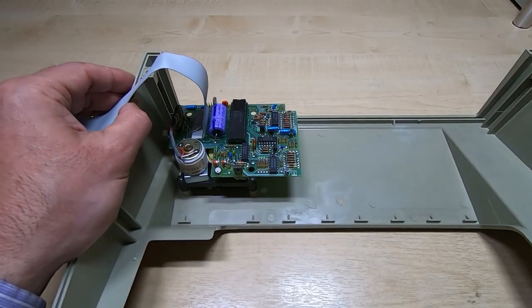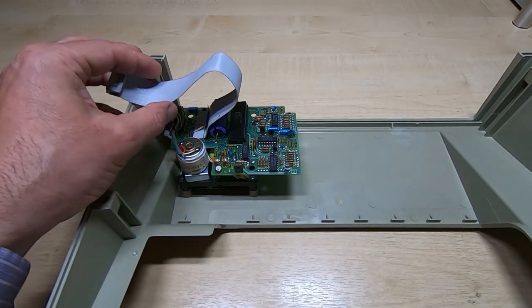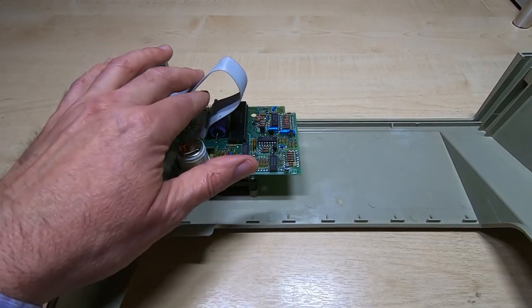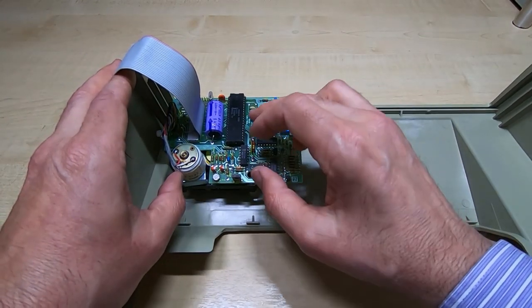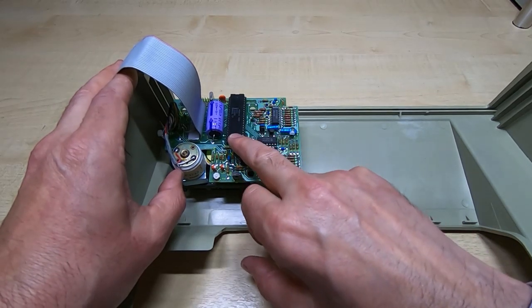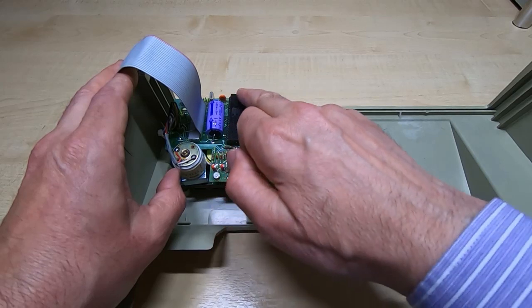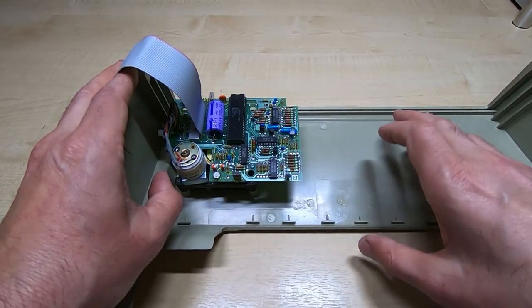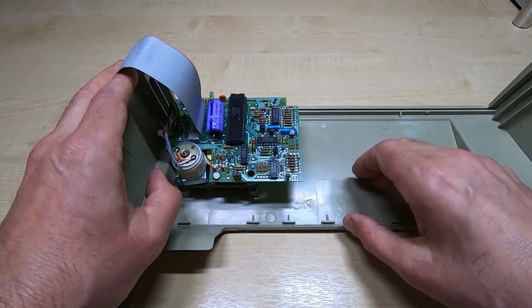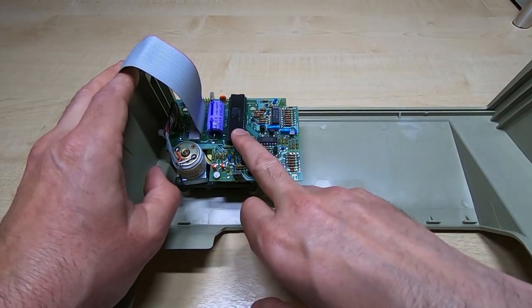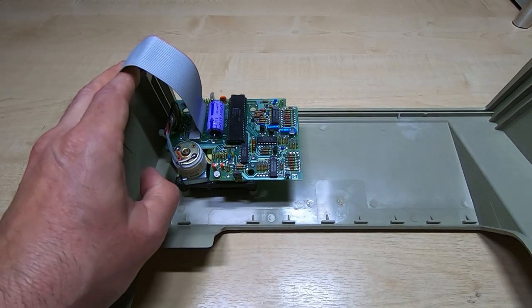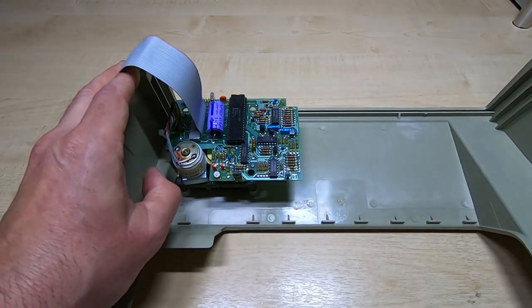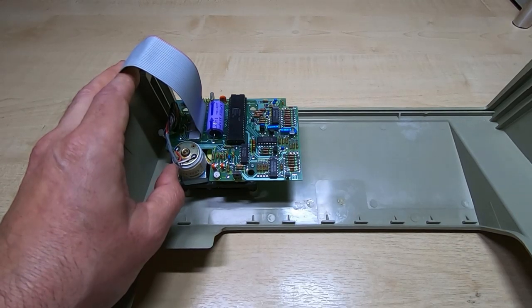So this is an 8041, and these are very interesting devices. It's one of the reasons why the component count on the main board for the Fluke is quite low. These are actually self-contained microcontroller systems. They're quite similar in their overall functionality to a Microchip PIC in that they have a peripheral interface and various ports, but they also have built-in EEPROM and built-in RAM, so this actually is a small computer system. The Fluke main board just sends a command to the tape drive—this is also used in the display and keyboard.